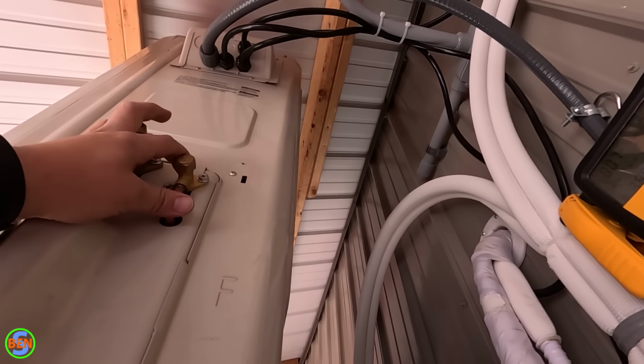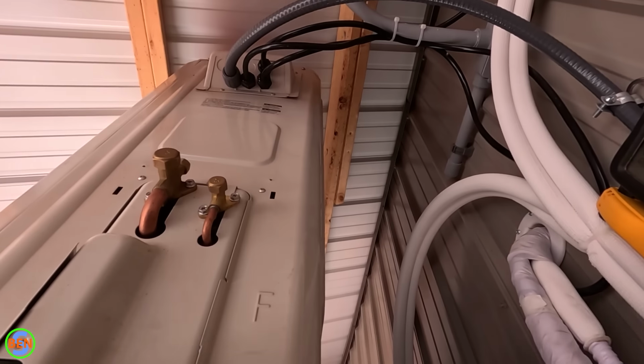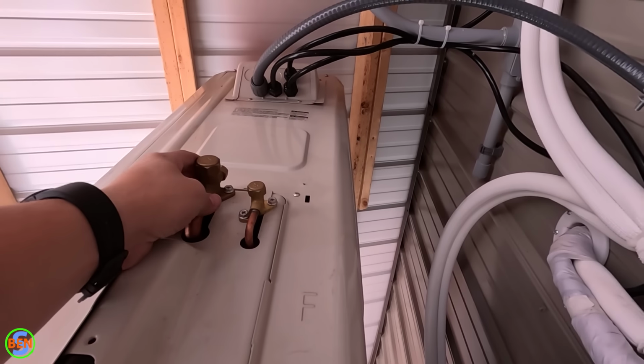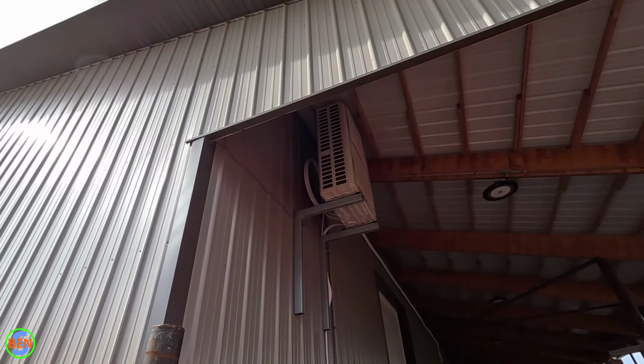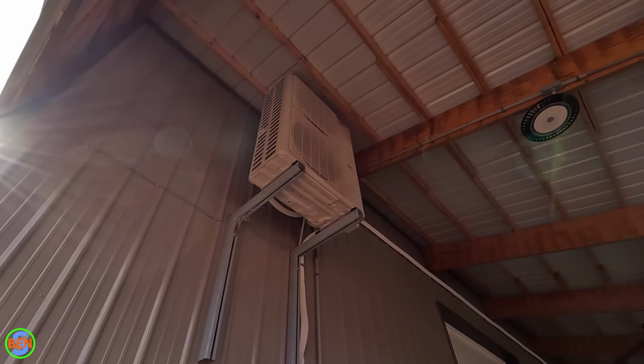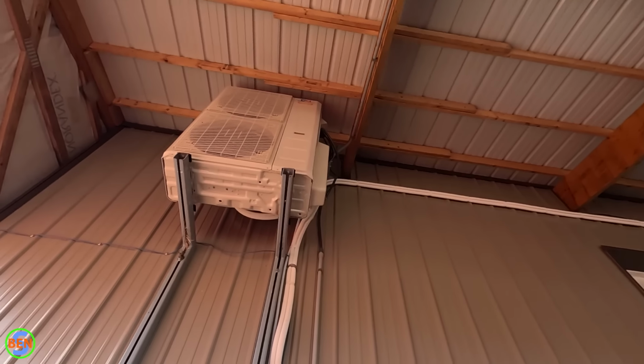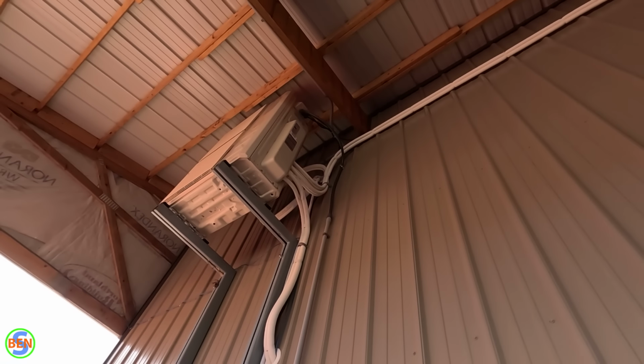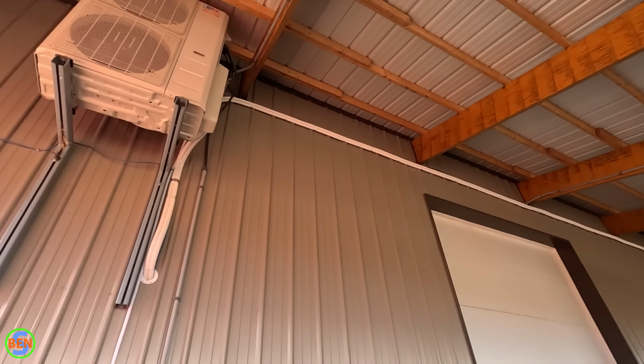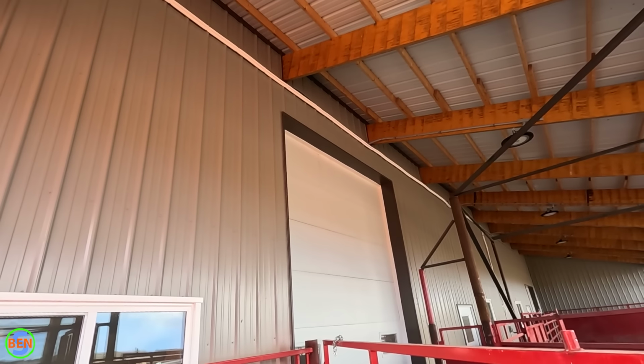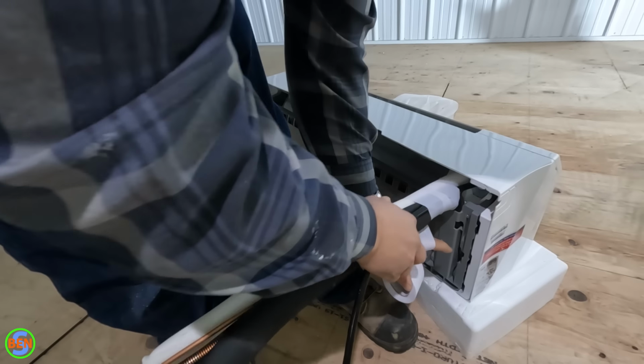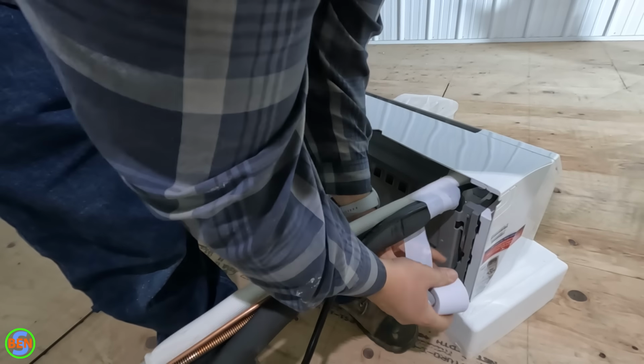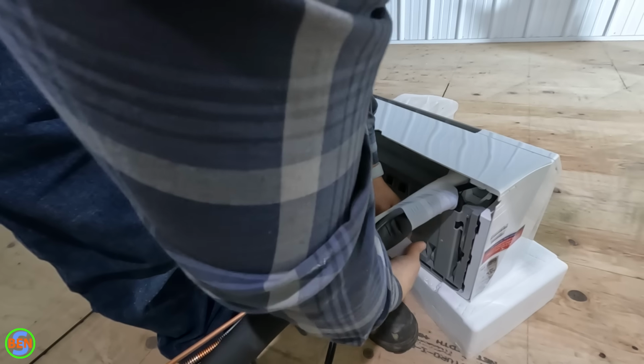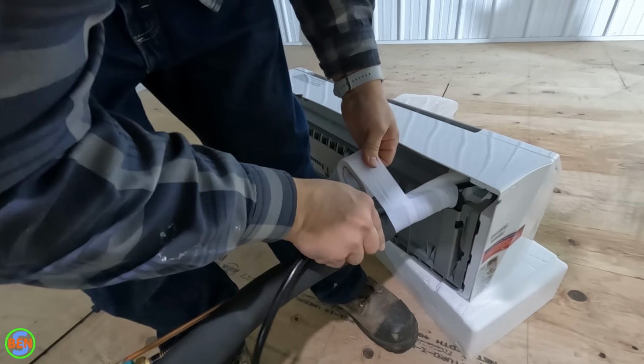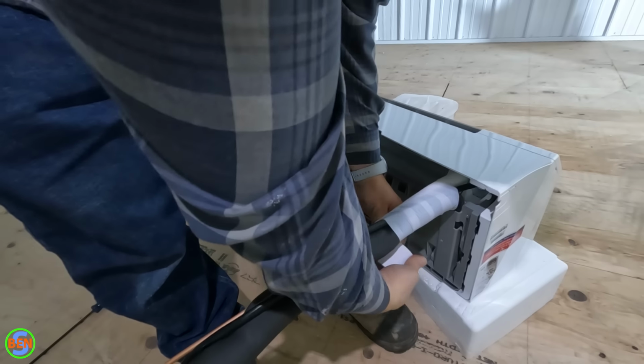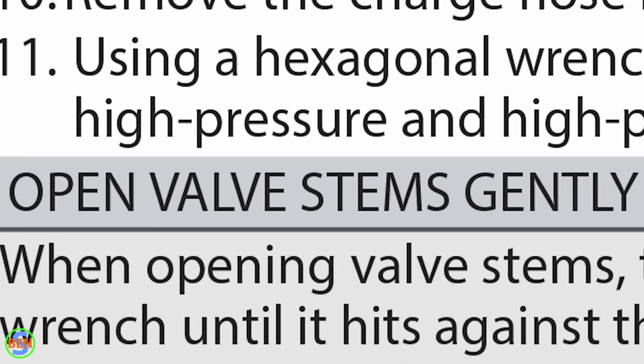But in all the units that I have installed, I have had a very difficult time getting them down to that level, and I know for a fact that I have no leaks. I think that there's a certain amount of off-gassing that can happen with some of the different O-rings and seals and components that are in the system that make it really difficult to achieve that 500 or sub 500 micron level. But comment down below if you have any other thoughts about that. But if it stabilizes around 700, then I am totally fine with saying this system is absolutely leak-free, and we are good to move on to opening the valves.